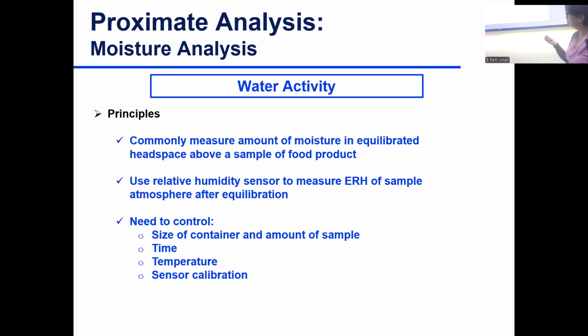So we use a relative humidity sensor to measure relative humidity at equilibrium. Basically, that's ERH, which is equilibrium relative humidity.